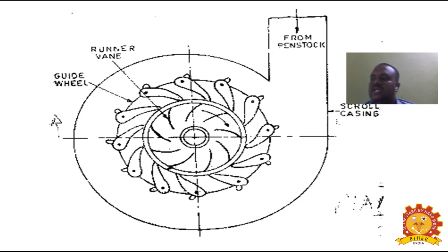The water enters the runner with low velocity and considerable pressure. As the water flows through the runner, the direction of flow is changed from radial to axial. The pressure energy is gradually converted into kinetic energy, and the runner is rotated at high speed. This torque is transmitted to the generator, which is coupled to the runner shaft. After passing through the runner, the water goes to the draft tube. Axial flow reaction turbines, like propeller turbines, have a rotating shaft and are vertical turbines. That is the explanation. Okay.